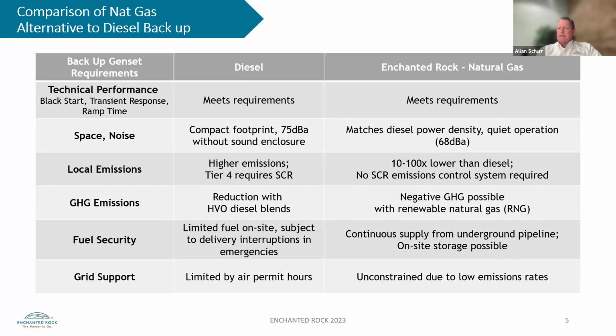It starts in less than 10 seconds. It can carry a variety of different load types and maintain utility grade power even when not connected to the grid. That's a very significant engineering challenge that diesel has been well tuned to do. If there's to be a substitute for diesel generators, it has to meet those technical standards or it won't be accepted. That's a commercial reality.